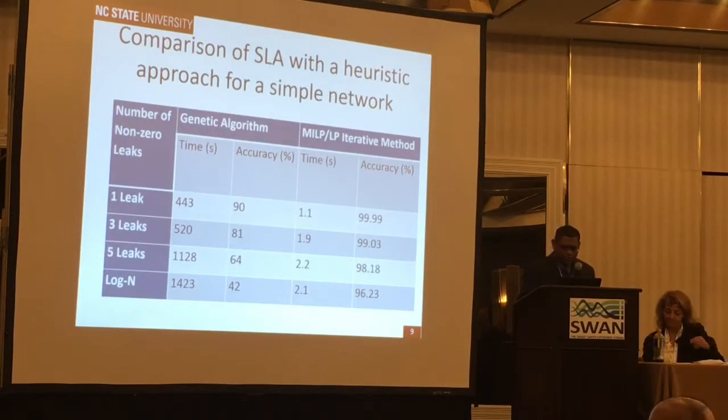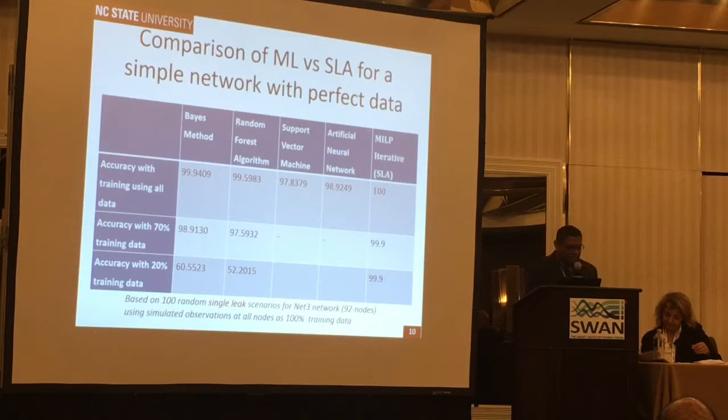On the leak detection side, I don't want to go into details because we are running out of time. One thing I wanted to show is, we experimented with both hydraulic model-based leak detection as well as pure machine learning. What we found was, if you use pure machine learning to do leak detection, without the information from a hydraulic model, our accuracy is not that good.